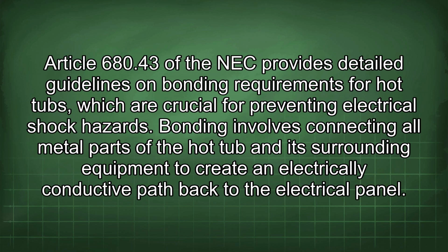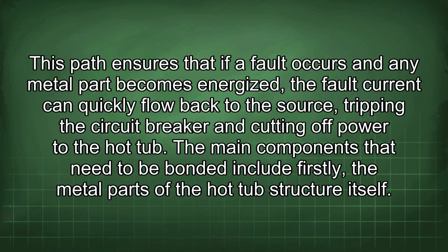Article 680.43 of the NEC provides detailed guidelines on bonding requirements for hot tubs, which are crucial for preventing electrical shock hazards. Bonding involves connecting all metal parts of the hot tub and its surrounding equipment to create an electrically conductive path back to the electrical panel. This path ensures that if a fault occurs and any metal part becomes energized, the fault current can quickly flow back to the source, tripping the circuit breaker and cutting off power to the hot tub.